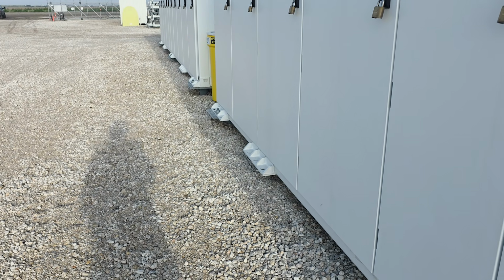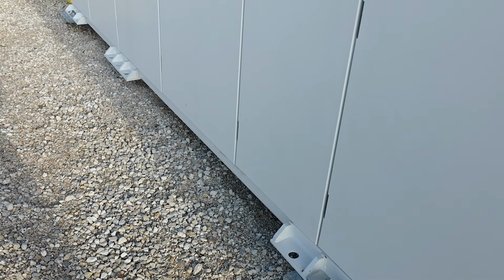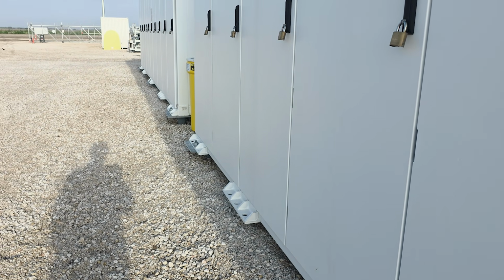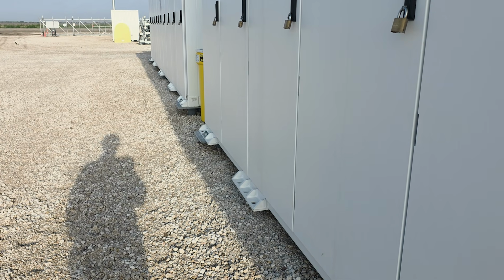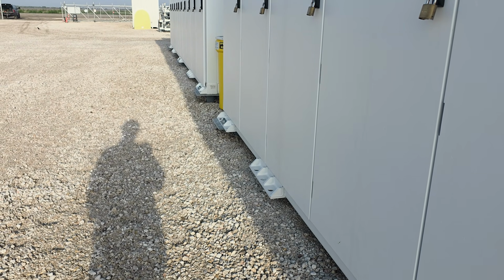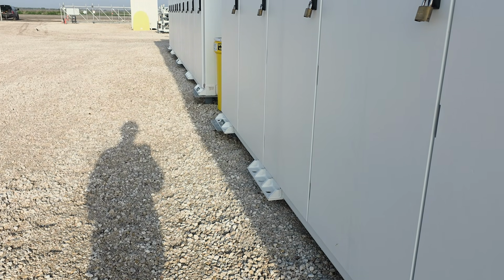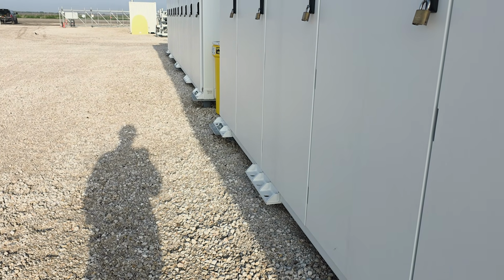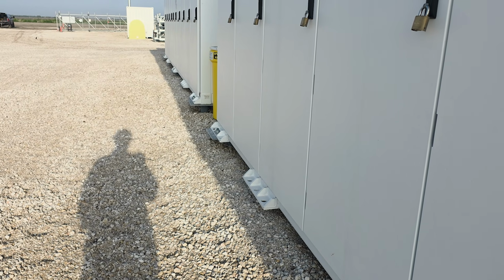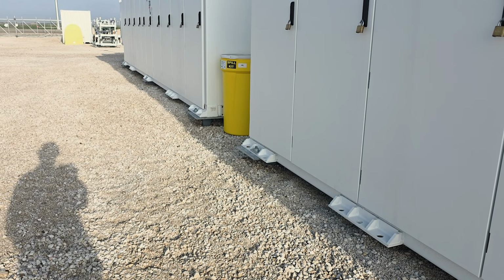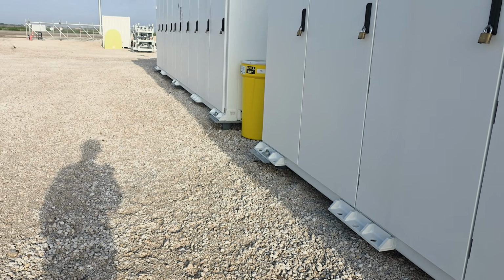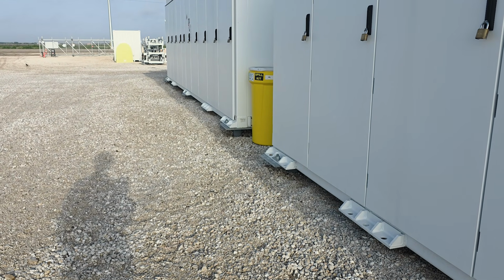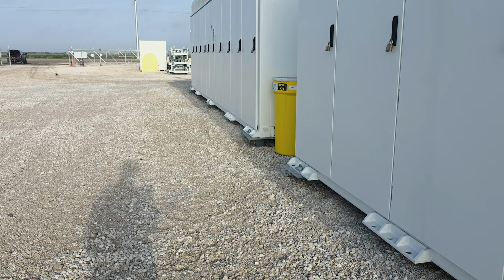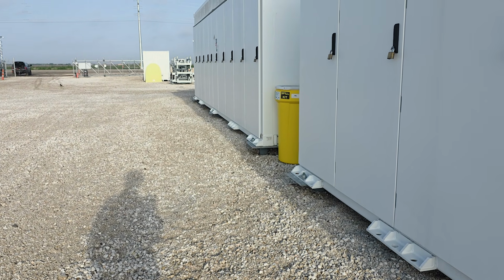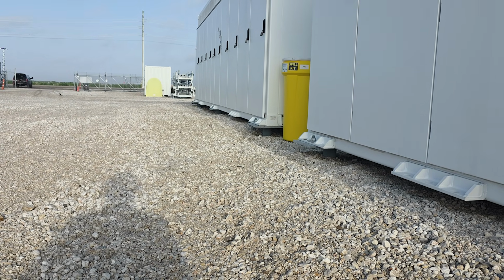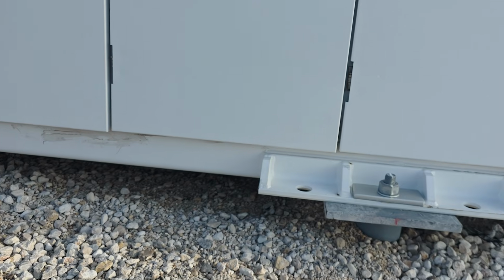So as you can see, these battery skids are placed on screw piles. We've seen these from long, narrow concrete foundations where there's 1 to 3 per battery, to screw piles like this, and also to the vibrated plates where you just vibrate I-beams into the ground 20 feet. So different foundation designs based on the soil situation they're in. Once these screw piles are screwed in, usually they screw in until they reach a certain torque, and that means that they are good. Then you have to come back with a laser level and cut off all of the screw piles that stick up, level them out, and then you have to weld the plates on. Those are the plates that you see here.